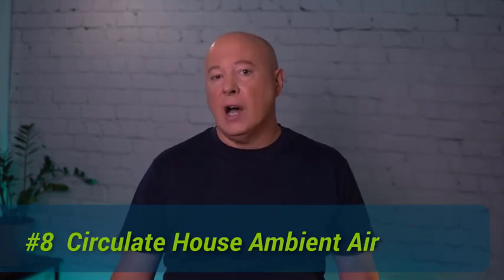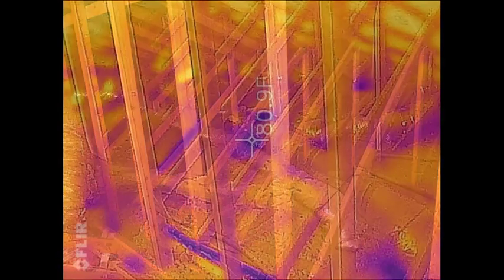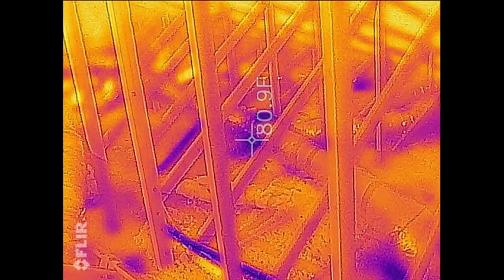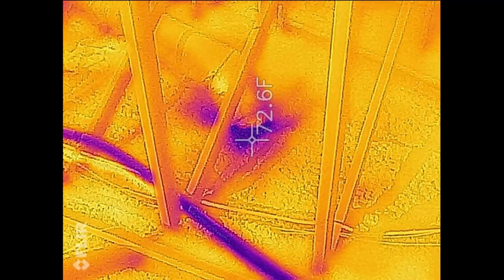Here's some photos of a hot Nevada attic where the blue spots clearly indicate duct leakage. But the AC is not actually on. If you look at the spot temperature reading in this close-up, you can see the air leaking out is at 72.6 degrees. It would have been more like 52 degrees if the AC were on.